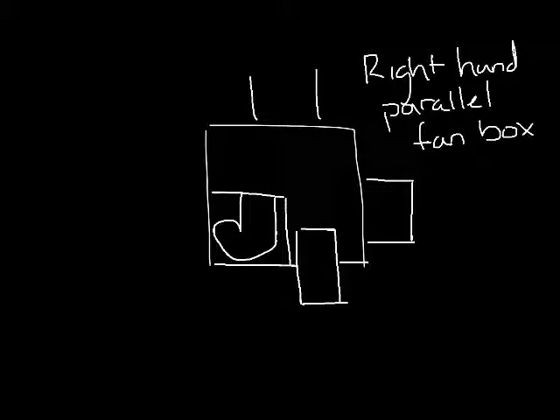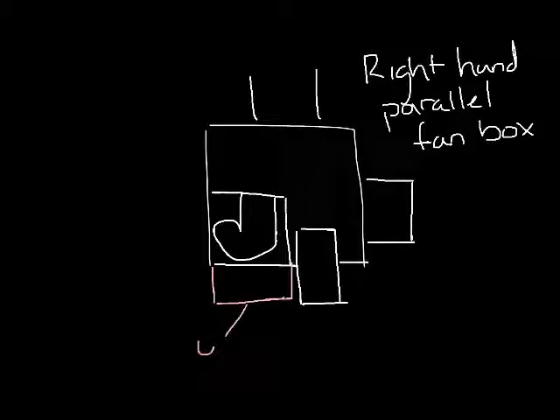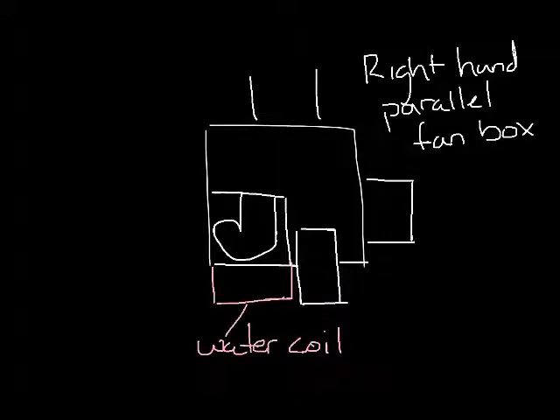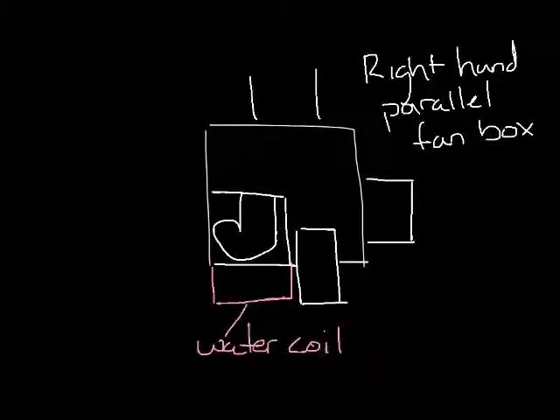To reduce the pressure drop of the fan box when the unit is in cooling, we often put the water coil at the induced air inlet. Now the box only sees the increased pressure drop when the unit is in heat and the fan is on.